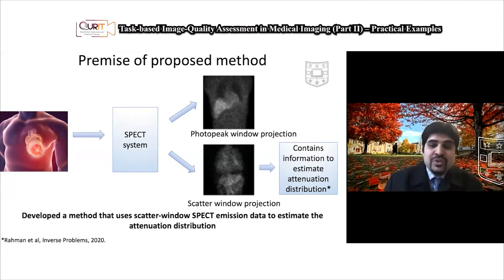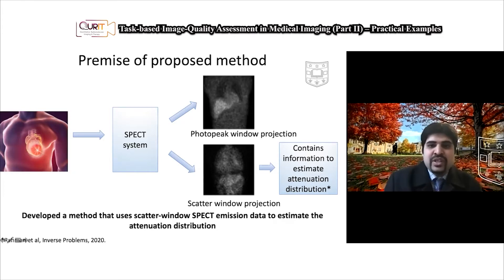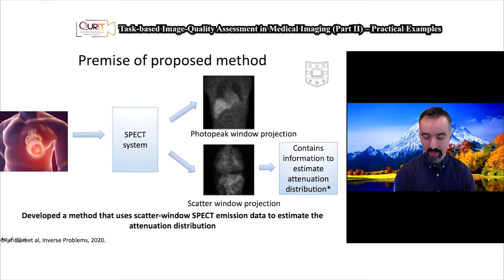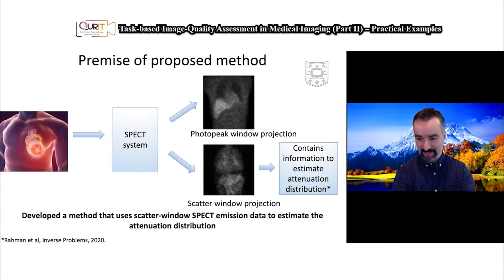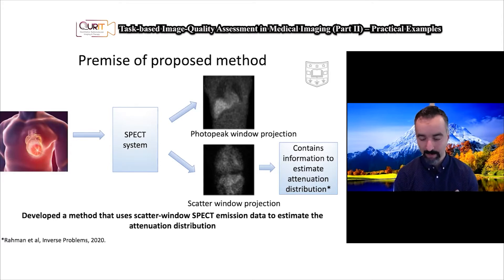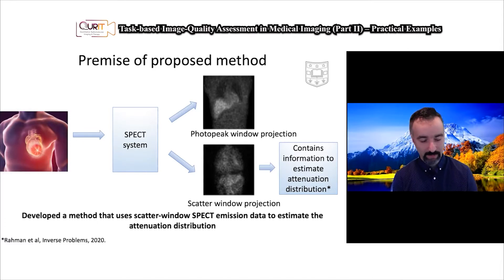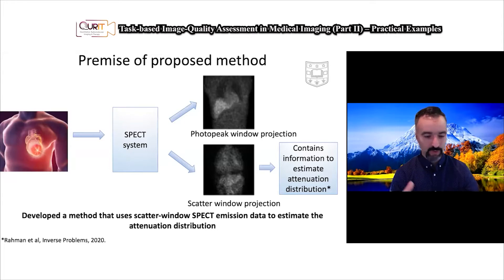We showed theoretically, using a Fisher information based approach, that these scattered photons contain information to estimate the attenuation distribution. We then used a method that uses the scatter window emission data to estimate the attenuation distribution. For those interested in the theory behind how we demonstrated this, I refer you to our publication in Inverse Problems. As noted in this course, people moved away from Chang correction toward CT-based systems, but this work takes a different direction — examining whether information in the lower energy scatter window that we tend to throw away can actually be used.